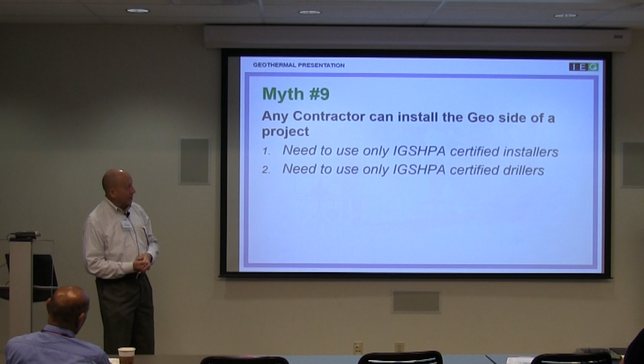I can't tell you how many times I've gotten a phone call from an engineer that says, well, we use 250 feet a ton, that's what it is in this market, and it's heating up. And I'm going, well, what'd you hook it up to? You've got it hooked up to a building that's running 24 hours a day. Well, no, it's not going to work. What's that 250 feet a ton equate to? What kind of building?